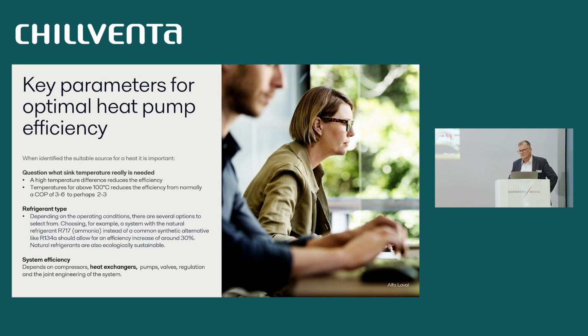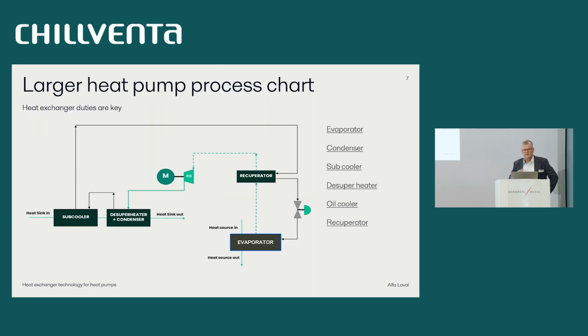Then of course there is the system design and the components included. There are compressors, and I'm coming to the heat exchangers, so we'll talk more about that. Pumps, valves, regulations and other things are also important. In a large heat pump there are many positions for heat exchangers, which we are working with: evaporators, obviously condensers, subcoolers, desuperheaters, oil coolers and recuperators. Sometimes several positions are combined into one heat exchanger, and we can make things very compact and very efficient.